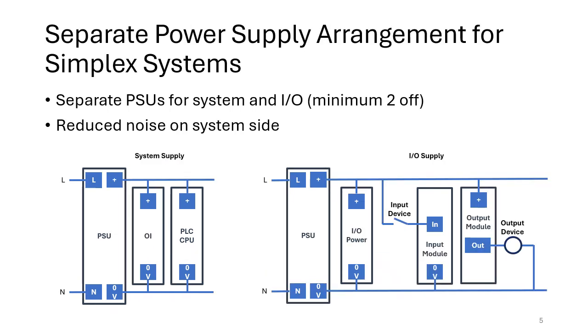It's common though to separate the power supplies even in simplex systems, and my preference would be at least 2 power supplies. So we'd have one power supply for the system, so that would provide, for example, the operator interface and the PLC CPU, and then we'd have a separate supply for the I/O. So there'll be a separate power supply which provides power to the I/O modules and the input devices and the output devices. 2 key reasons for doing this.